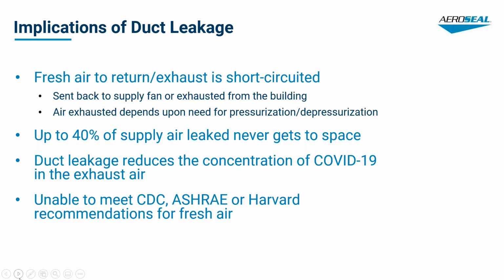So, you think about some of the slides that we had at the beginning. ASHRAE tells us that 75% of ducts leak 10 to 25%. The studies show light commercial is especially leaky, 10 to 30%, right? So this is something that's widespread. It's not something that is happening in just a few buildings. It's not happening only in old buildings. This is happening all over the place. And so every time you're opening those dampers, every time you're running those fans or bringing in more fresh air, that doesn't necessarily mean that it's making it to the space and that you're meeting those requirements that are needed to keep the spaces healthy for those occupants.